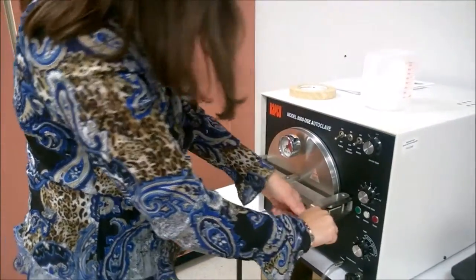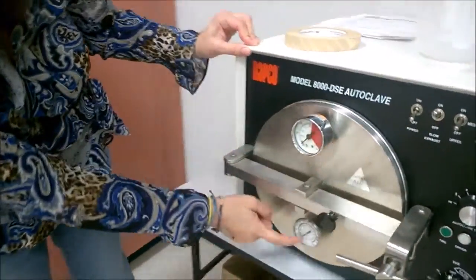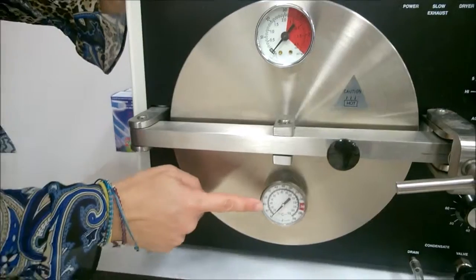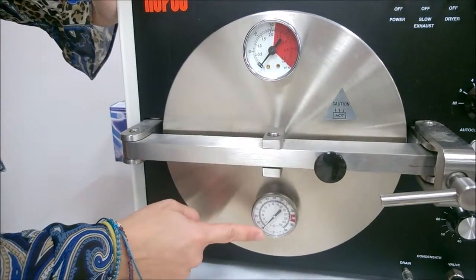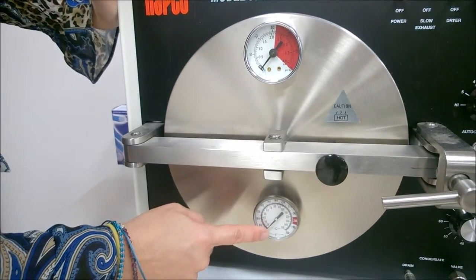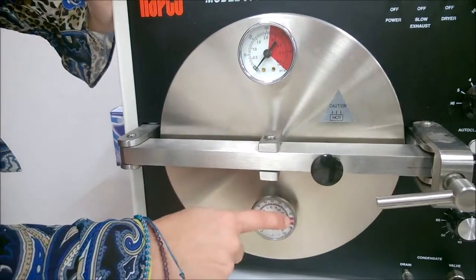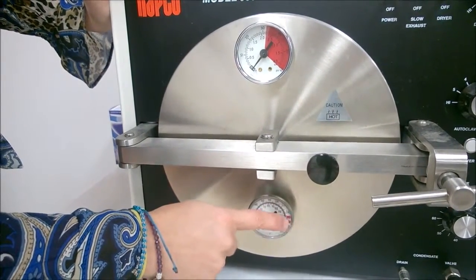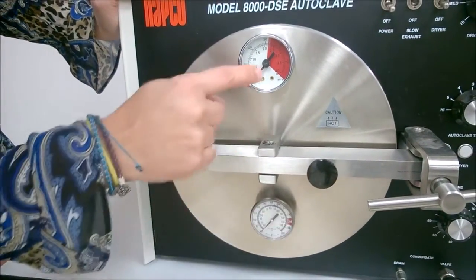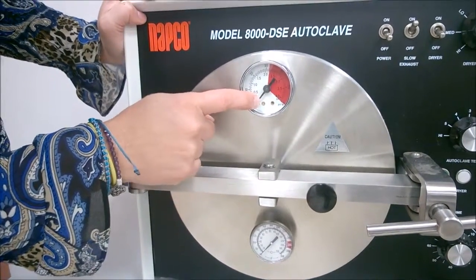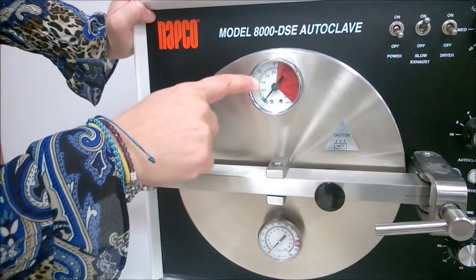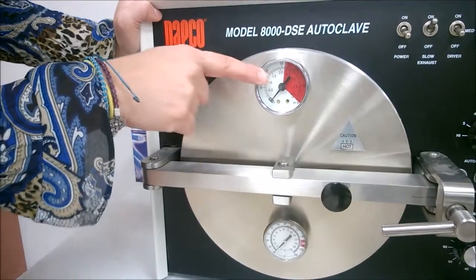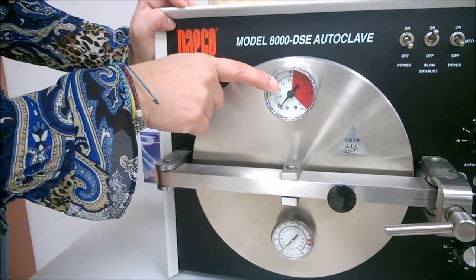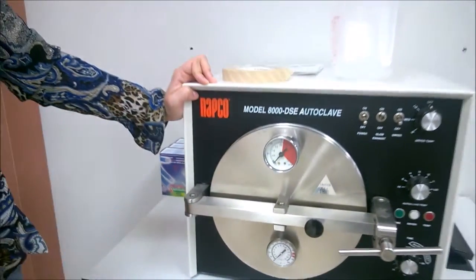completely. And if we can take a look at this area and this area right there, these are the temperature indicators. This particular temperature indicator is going to go all the way up to 121 degrees Celsius, which is the red spot right there. And then this is the pressure indicator, and it's going to go all the way up to 15 psi once we reach the desired atmospheric pressure.